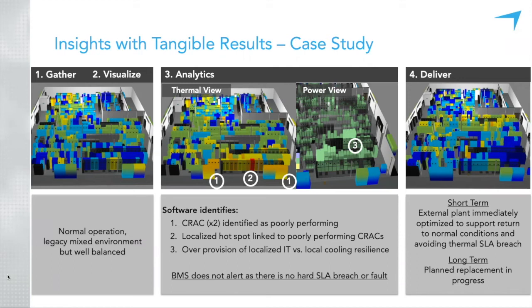Classically in these case studies, over time the learned behavior goes into the software, and then there is a change. In this case, the change is the degradation in performance of one of the air handling units, which happens to be associated with the worst possible place in the room, where it's very highly loaded and the overall resilience is quite low anyway. Building all these things together allows us to give true insights and very early warning to customers of potential problems, which is particularly helpful in these applications where time is critical because the loadings are significant and there's not a lot of margin for error.